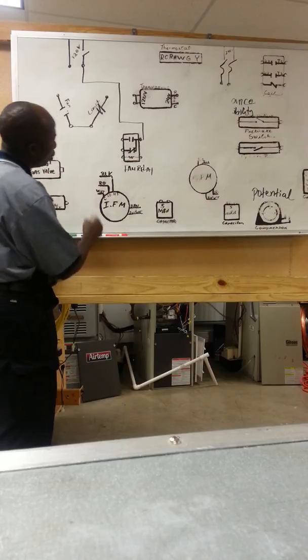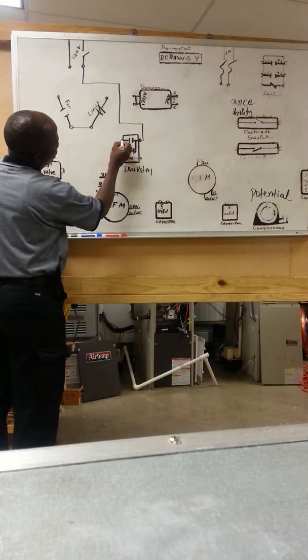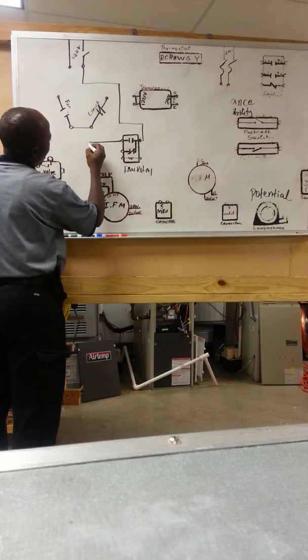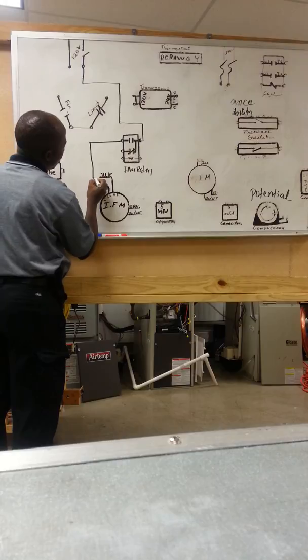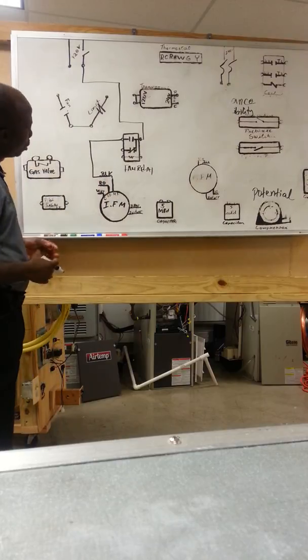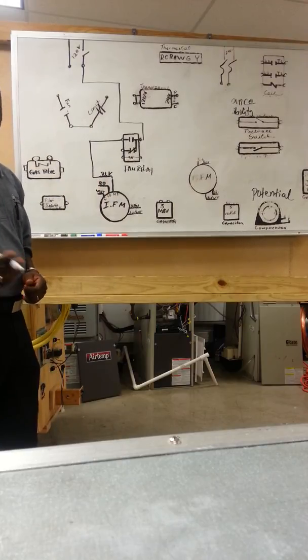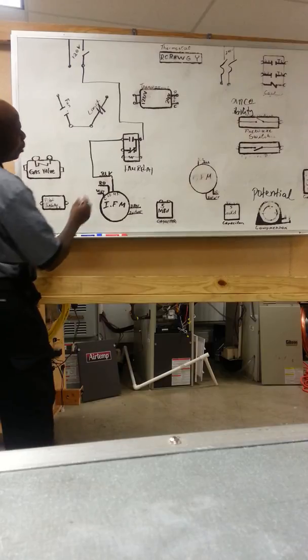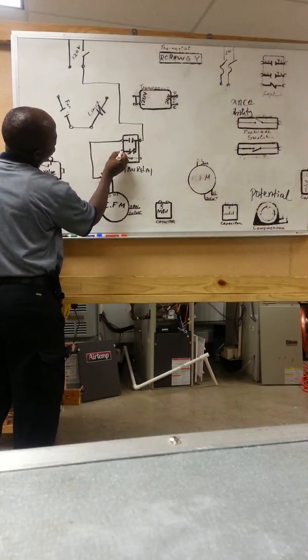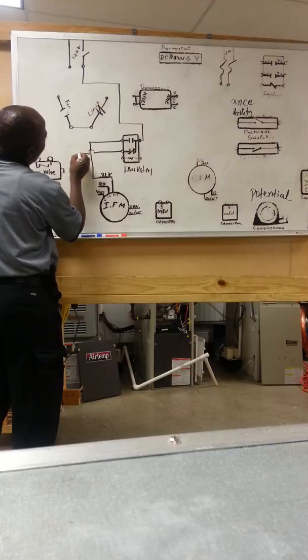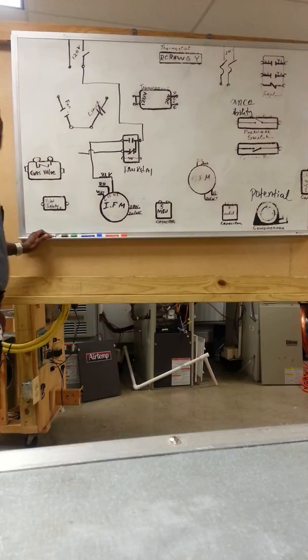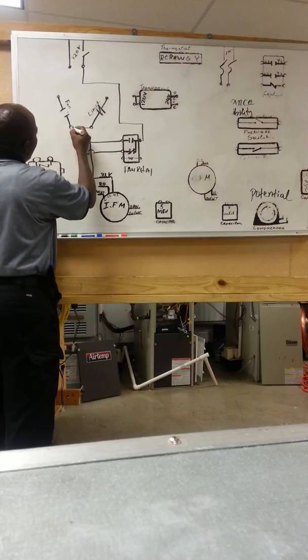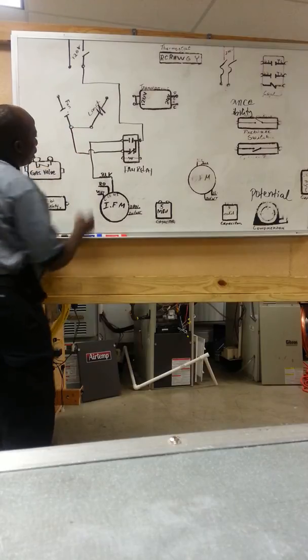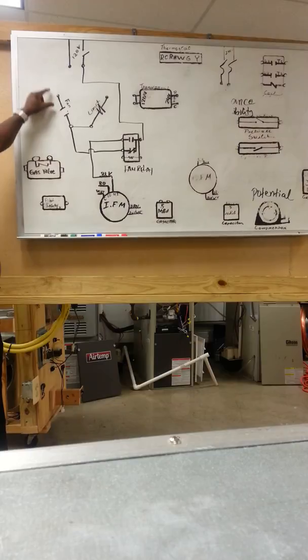So what we're going to have to do, we're going to get power from the normally open, which is going to be the black wire, coming down to the cooling wire, the black wire, which is high speed for cooling. And we're going to get power from the normally closed, which is power coming out, and we're going to feed power into the fan center on the combination fan and limit switch. Now we have power coming in here, but there's no power going through because this is normally open.